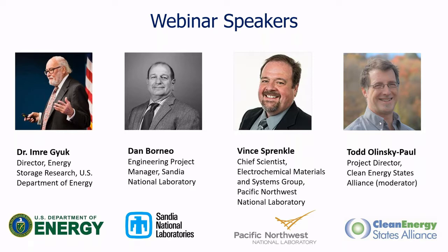They can serve all applications, just like any other battery, especially when you get into advanced lead acid with that carbon component. With that carbon component you can do a lot, like frequency regulation with a very shallow discharge cycle, getting many, many cycles out of it. It's still to be determined how that compares with lithium ion at the same depth of discharge. They can also do energy applications, but the problem is their energy density is much lower, so you need more of them. Currently, among the favorite applications are backup for server farms and banks, and telecommunication towers.